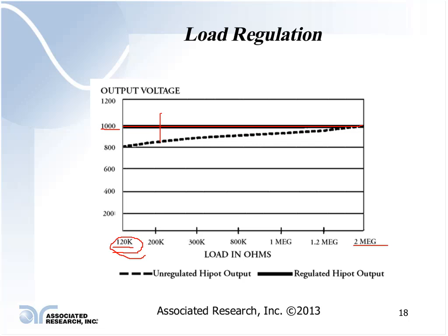I must maintain that minimum value, because that allowed me to set this voltage a little higher at varying load conditions, as long as it did not drop below the 1,000 volt potential to the point where I generated a failure.